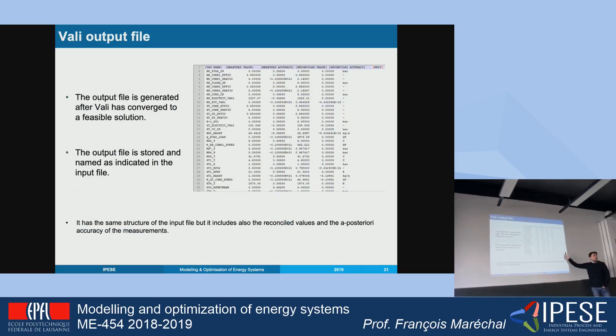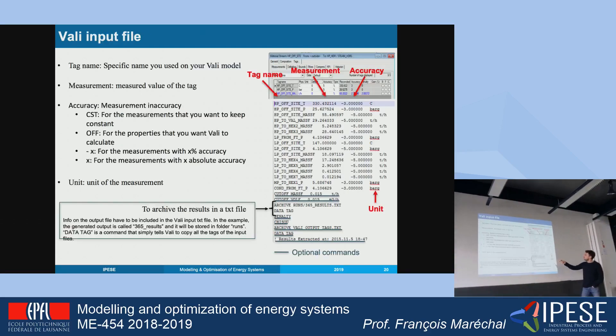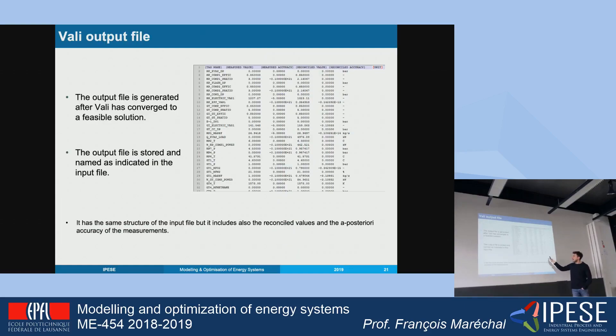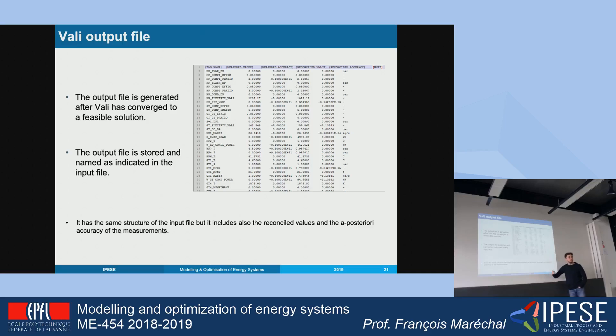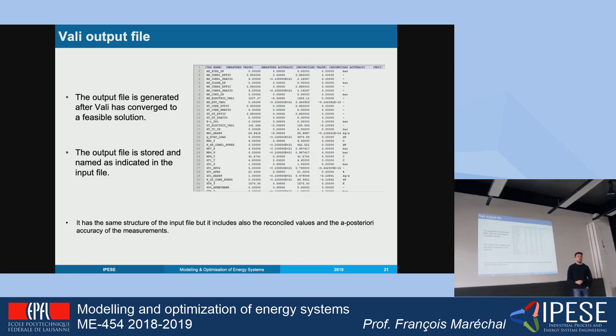In the output file you have the same list of tags. You see the measured value, the accuracy you provided, and the reconciled and validated value. There is also a posteriori accuracy — once you reconcile the value, a new accuracy is calculated and suggested to the user as an updated accuracy for that measurement.